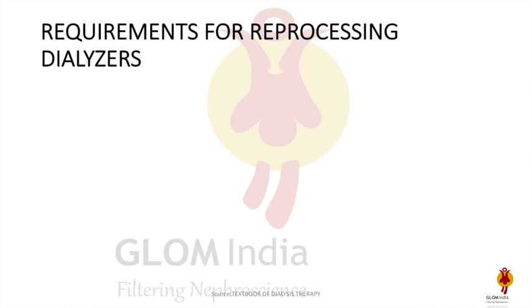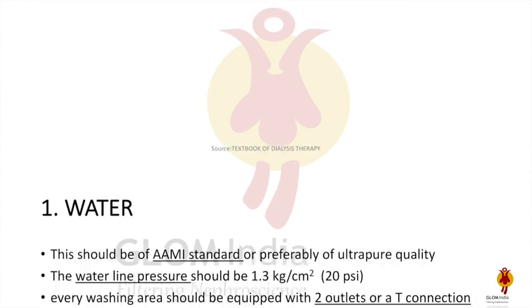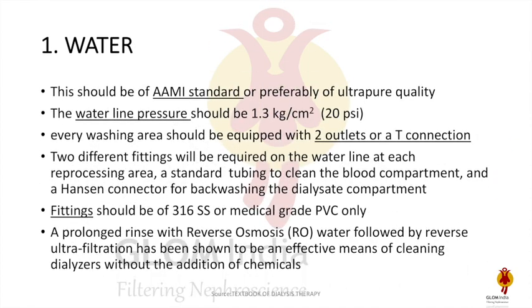The first requirement for reprocessing is water. The water should be as per AAMI standards and preferably ultra-pure quality. The water line pressure should be at least 20 psi. The washing area should have either two outlets or a T-connection: one for the blood compartment, where standard tubing is adequate, and one for the dialysate compartment, where a Hansens connection is required.